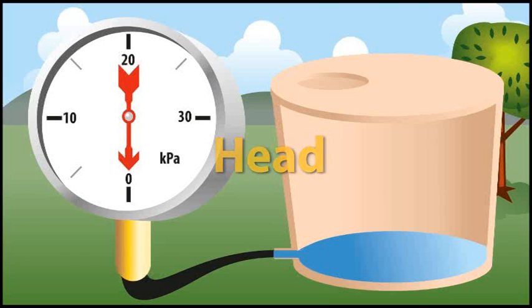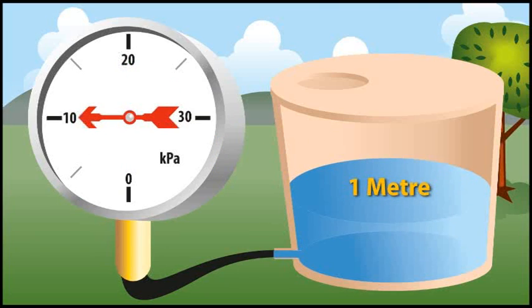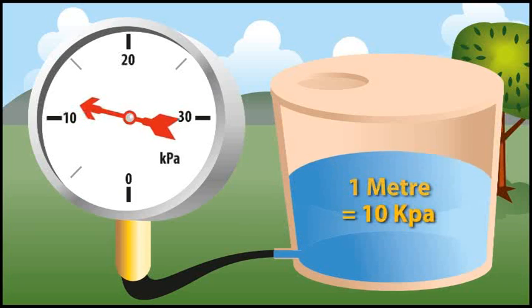In a tank where the water level was one meter higher than the outlet point, a pressure gauge would show 10 kPa of pressure, which is one meter of head. Every meter of water height equals one meter of head.